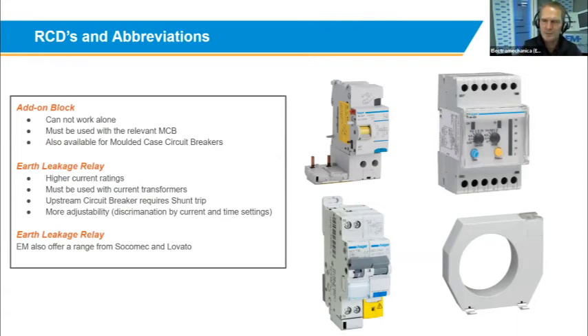So for earth leakage protection discrimination, you can start off with a 500 milliamp setting at your main breaker, go down to a 300 milliamp breaker, and then even go down to your block circuits, which will give you 30 milliamp. Then also for discrimination purposes, you've got more flexibility, because you can do the settings on time as well as on the milliamp settings on the device. So you've got a lot more flexibility around this. And just for interest sake, as Electromechanica, we also offer similar products from Socomec as well as Lovato that do the same thing.